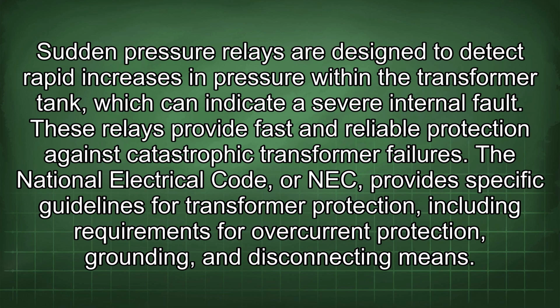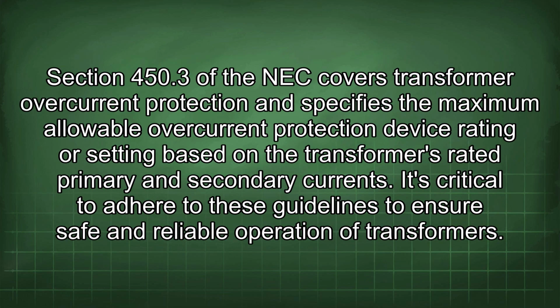The National Electrical Code, or NEC, provides specific guidelines for transformer protection, including requirements for overcurrent protection, grounding, and disconnecting means. Section 450.3 of the NEC covers transformer overcurrent protection and specifies the maximum allowable overcurrent protection device rating or setting based on the transformer's rated primary and secondary currents. It is critical to adhere to these guidelines to ensure safe and reliable operation of transformers.